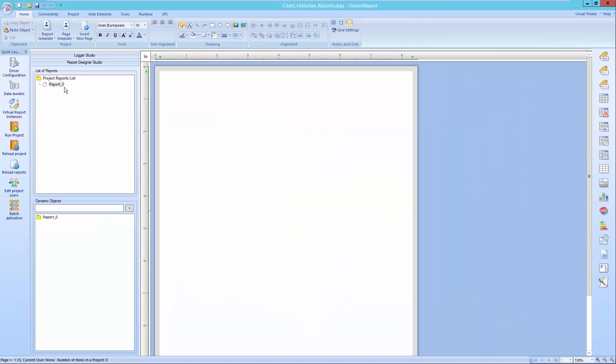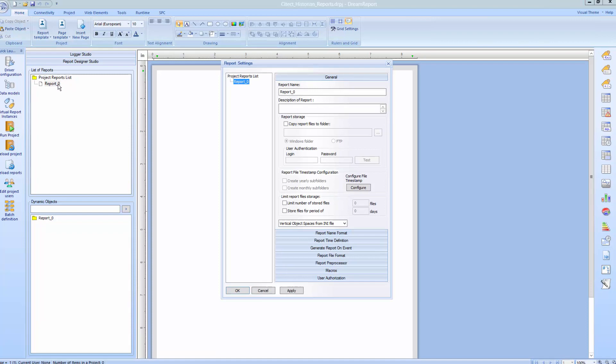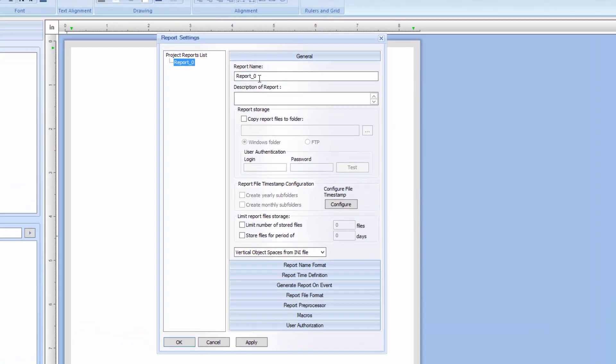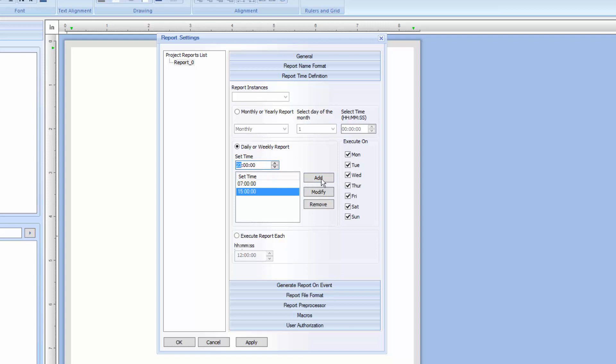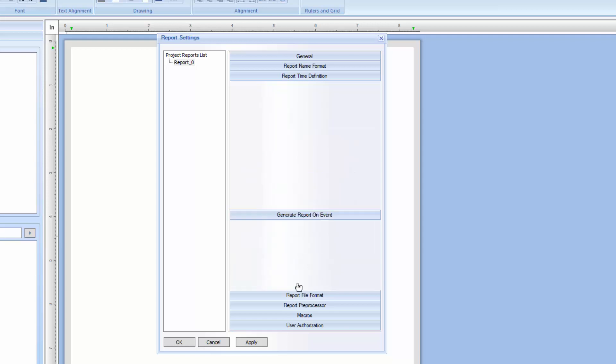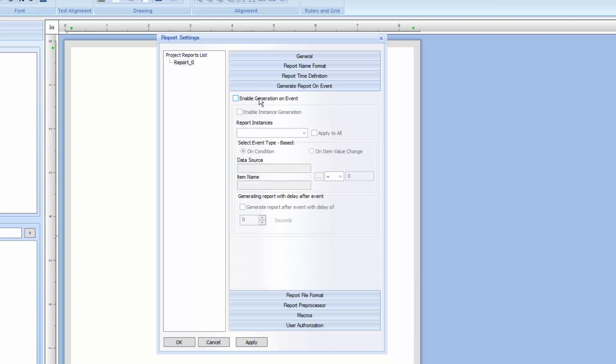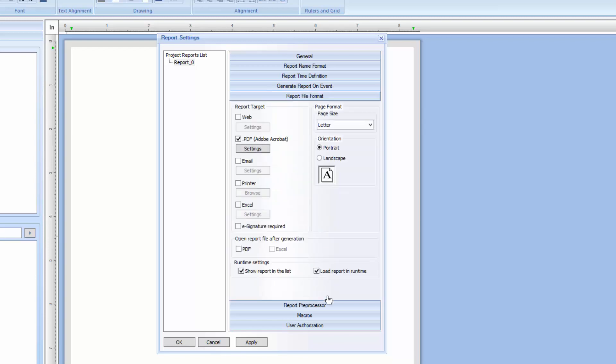Let's create a new report. We'll start with the default report, report 0, and give it a name. We'll call it SciTech historian shift report. Let's leave most of the defaults, but we'll change the report generation time to be at the end of every shift: at 7am, 3pm, and 11pm. We could also trigger the report to be automatically generated on an event. This is where we could use any real time tag from the SciTech HMI or a PLC, for instance, for the report generation trigger. Finally, I'll set the report format to be both PDF and web, and set the option to open the PDF after generation.